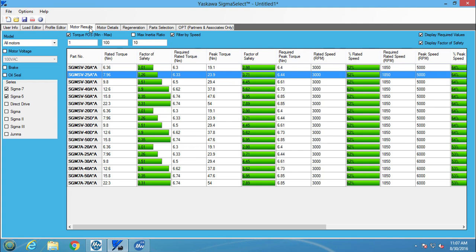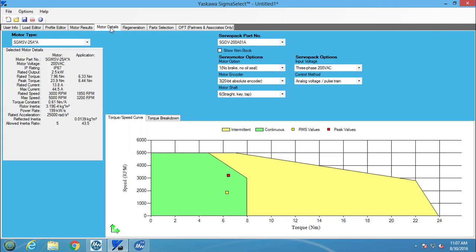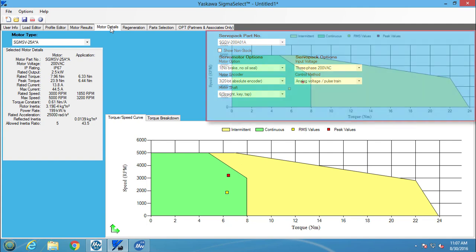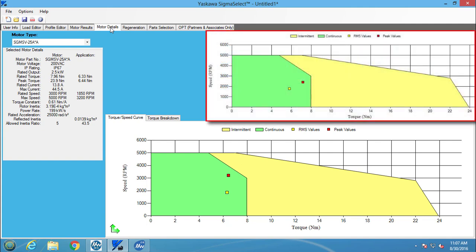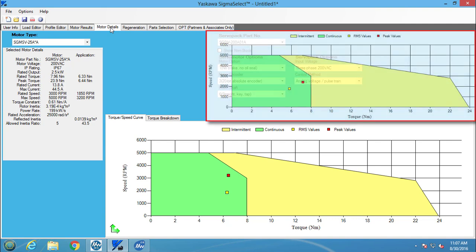The SGMSV-25A seems appropriate and is still selected from before. Now if I go to the motor details screen, I can see where the intermittent and continuous torque values sit on the torque and speed curve graph. You can see how the RMS and peak values are in about the same place as the original approximation, but this new profile from CamEditor is more accurate.